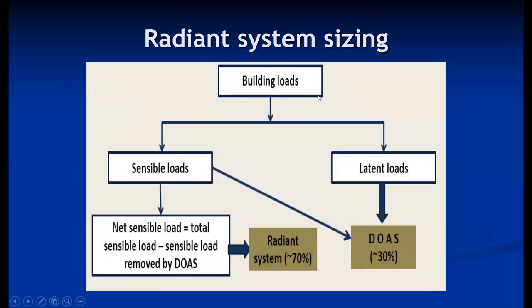Radiant system sizing is mainly determined based on the building load, which is categorized into sensible loads and latent loads. The sensible load handled by the radiant system is the total sensible load minus the sensible load removed by DOAS — the Dedicated Outdoor Air System — which is primarily a ventilation system. The radiant system carries 70 percent of the sensible load, while DOAS handles 30 percent of the sensible load and takes care of the latent load.